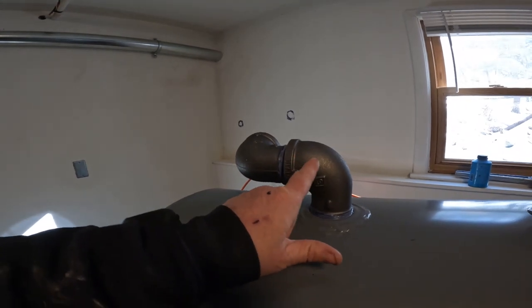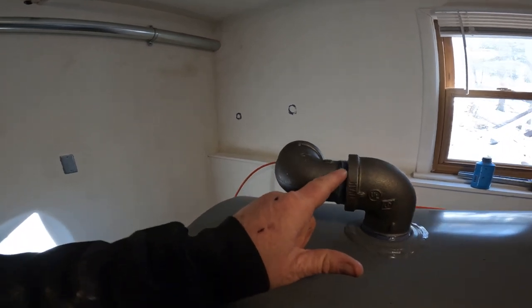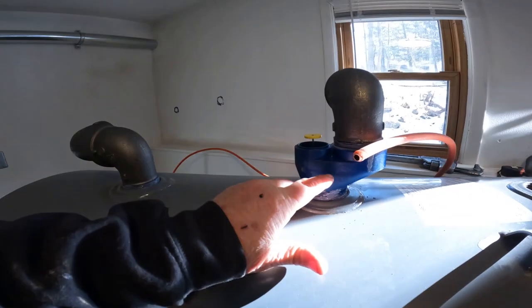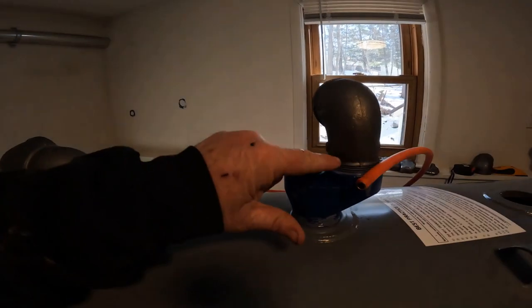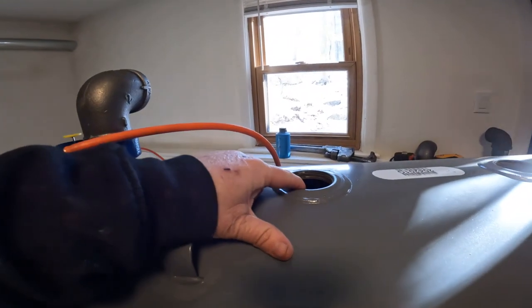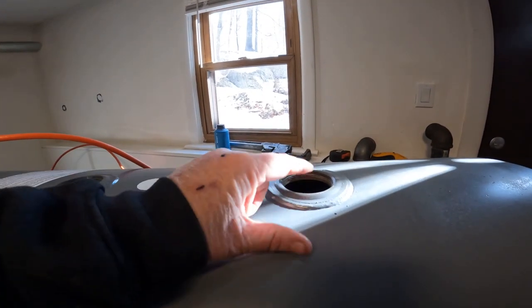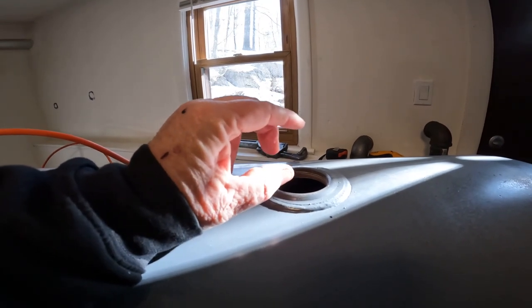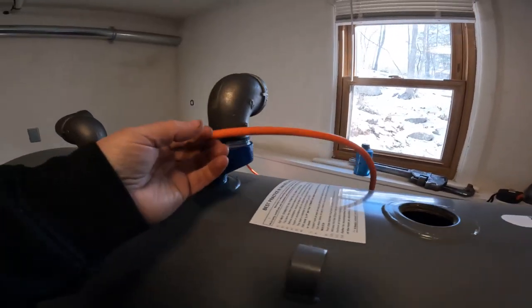We'll need a 90 swing joint coming up and out. That's a male to a female. And then another one, male to a female. We'll need a vent alarm sight gauge combo. And then we'll need another swing joint up and out. You'll need a 2-inch plug. You'll need a 2-inch duplex with the copper flared fittings, and they're going to be 1/2 inch in this case.